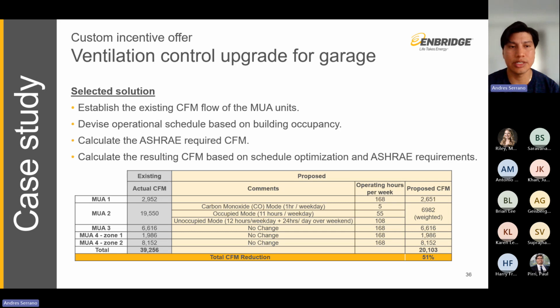So the selected solution in this case was to establish first the existing CFM flow to the makeup air units, devise an operational schedule based on building occupancy, calculate the ASHRAE required CFM, and calculate the resulting CFM based on schedule optimization and ASHRAE requirements. So this table here breaks down the makeup air units.